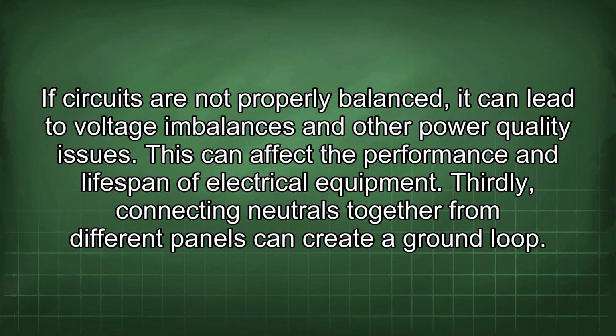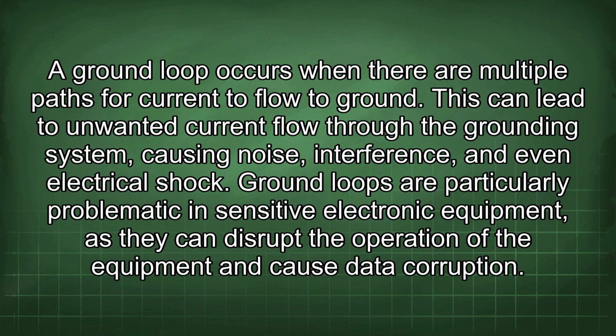Thirdly, connecting neutrals together from different panels can create a ground loop. A ground loop occurs when there are multiple paths for current to flow to ground. This can lead to unwanted current flow through the grounding system, causing noise, interference, and even electrical shock. Ground loops are particularly problematic in sensitive electronic equipment, as they can disrupt the operation of the equipment and cause data corruption.